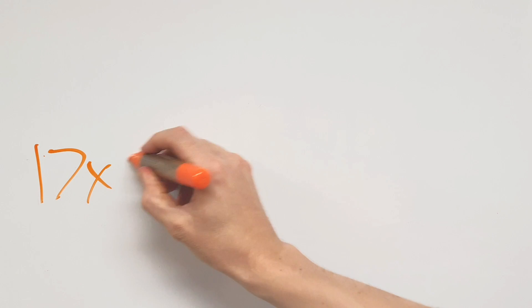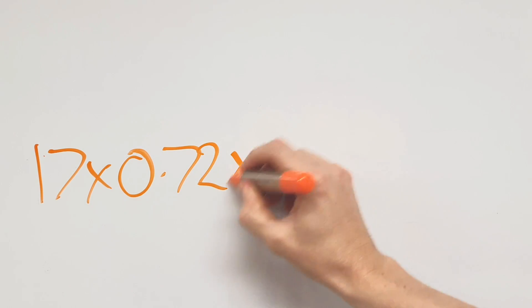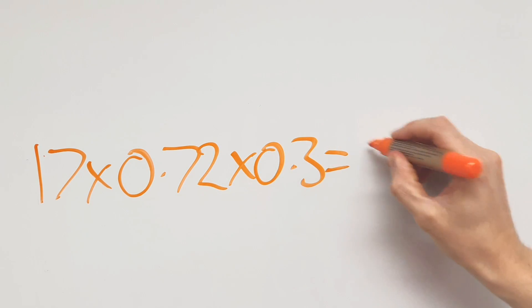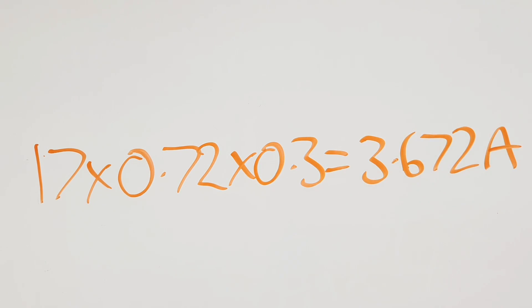So if your tabulated current carrying capacity was 17 amps, multiply it by the grouping factor of 0.72 and by 0.3, and you get 3.672 amps. If the circuit should never draw more than that value of current — for instance if it's feeding a fixed amount of light fittings — then you don't need to include it in your grouping factor calculation.